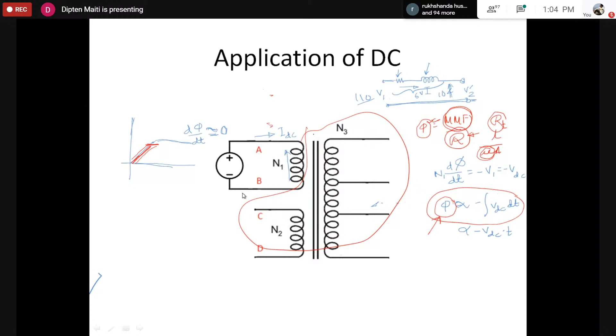Now there's a point for you to parallel the electric. We have already connected the two primaries in parallel. Now we have to load the transformer on the secondary. This can be done, but while connecting them in parallel, we have to consider the dot polarity, whether the dotted terminals are connected together and non-dotted terminals in parallel. Then we have to measure the current through the two coils, ensuring the current through each coil doesn't exceed its rated capability, and also measure the load current.